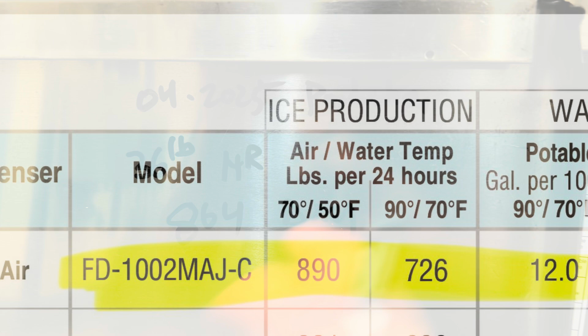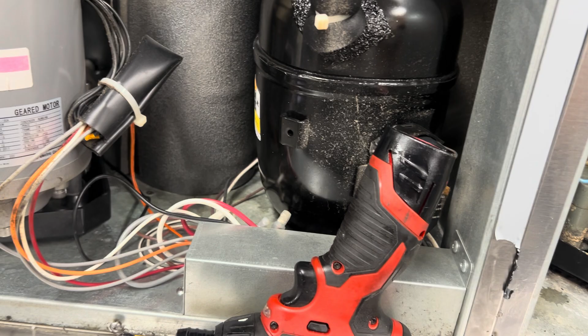So based on temperature fluctuations, it should be between 720 and 890, and it's doing pretty damn good. So with this, the left one is doing the heavy lifting, and the left one was off just the breaker, or the outlet is popped. That's why they were running out of ice. We don't have a mechanical problem.